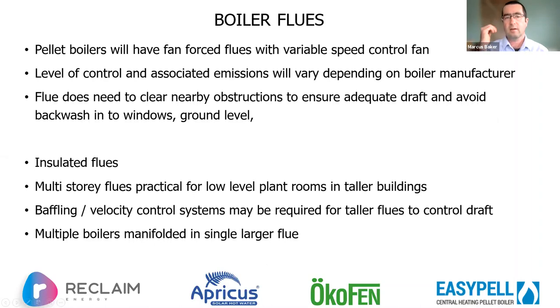The fluing: they're fan forced, with variable speed control. The emissions: somebody asked about particulate matter size and type. That will probably be addressed here. The controls and the emissions will vary depending on boiler manufacturer, but as you pointed out in your question, Daryl, they're pretty much all from Austria, one from Switzerland, of the examples that I found, and so they all have to meet the European requirements. So I wouldn't suspect any would have any issues in this country.